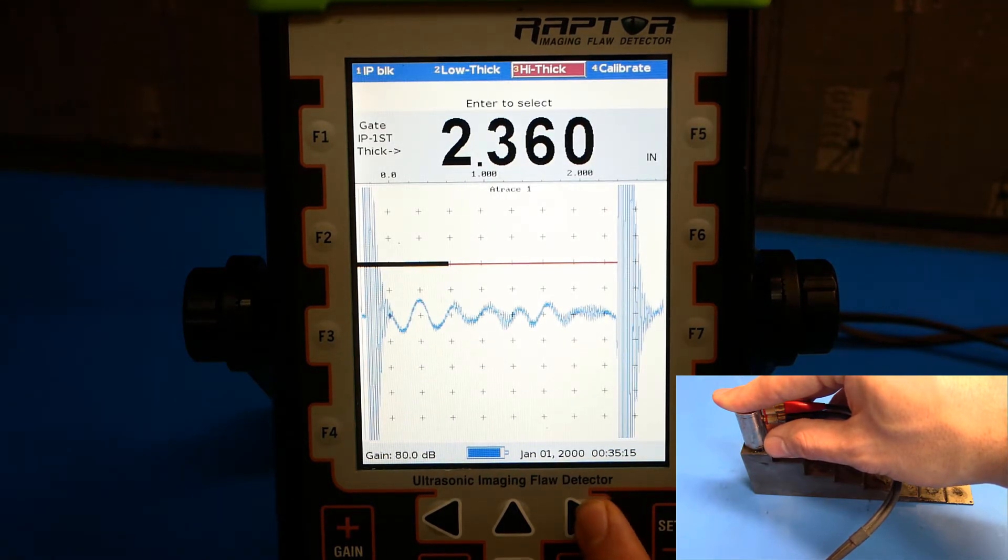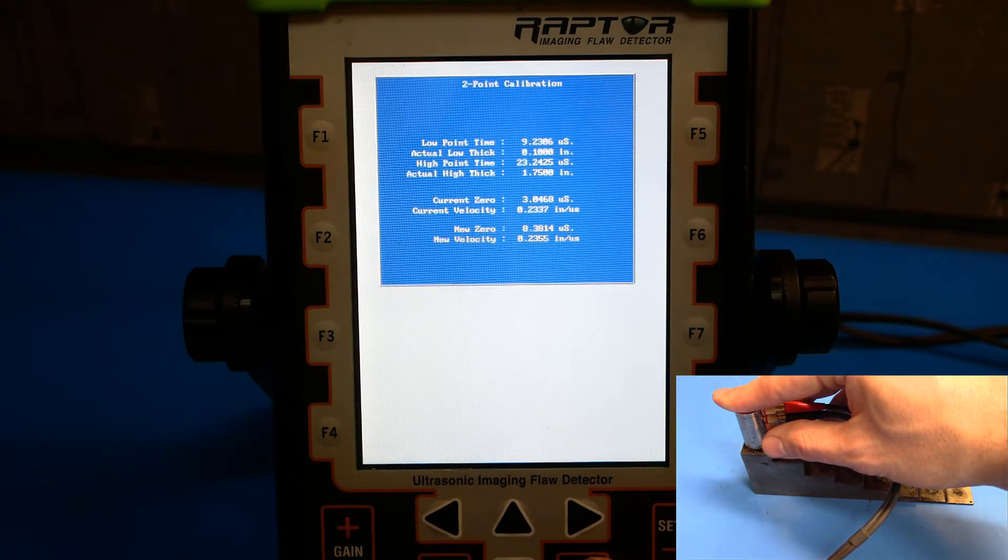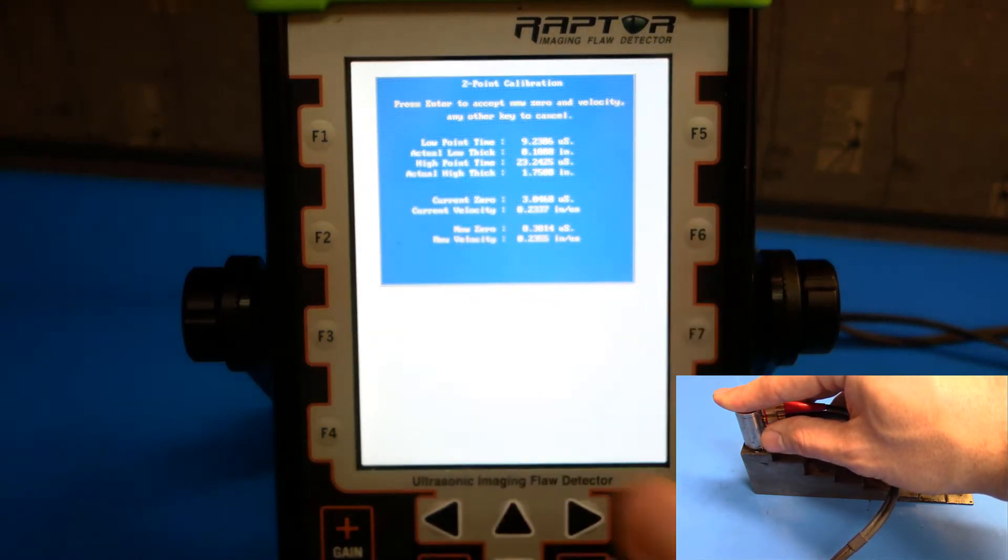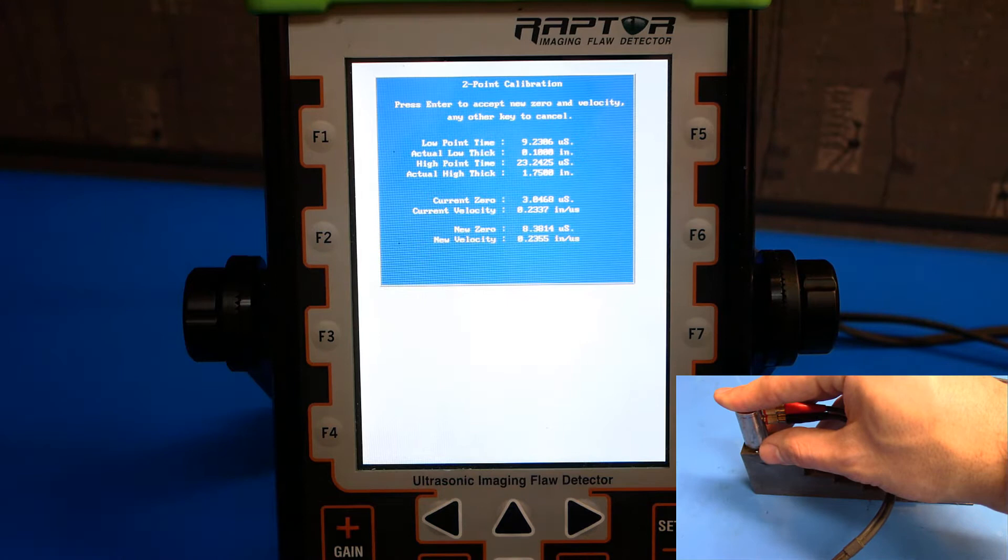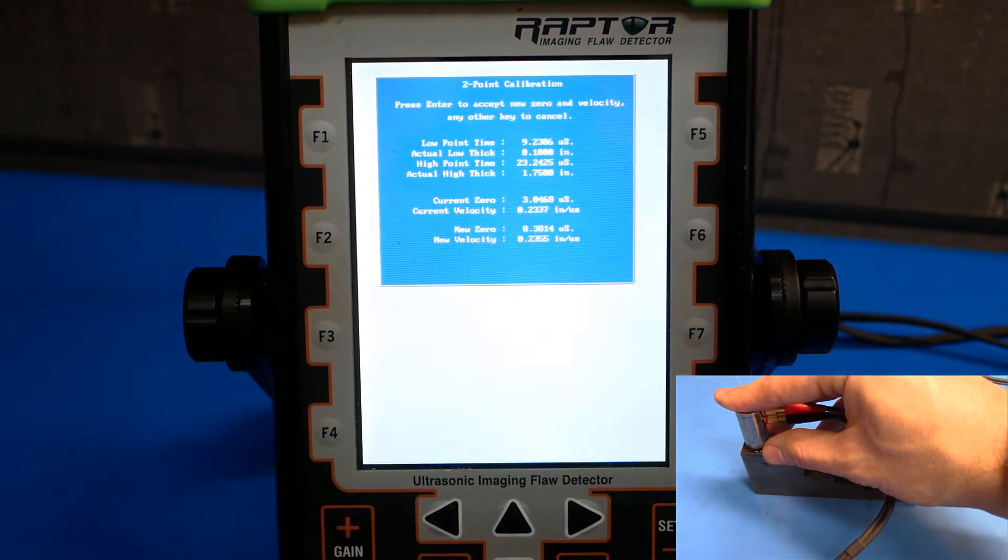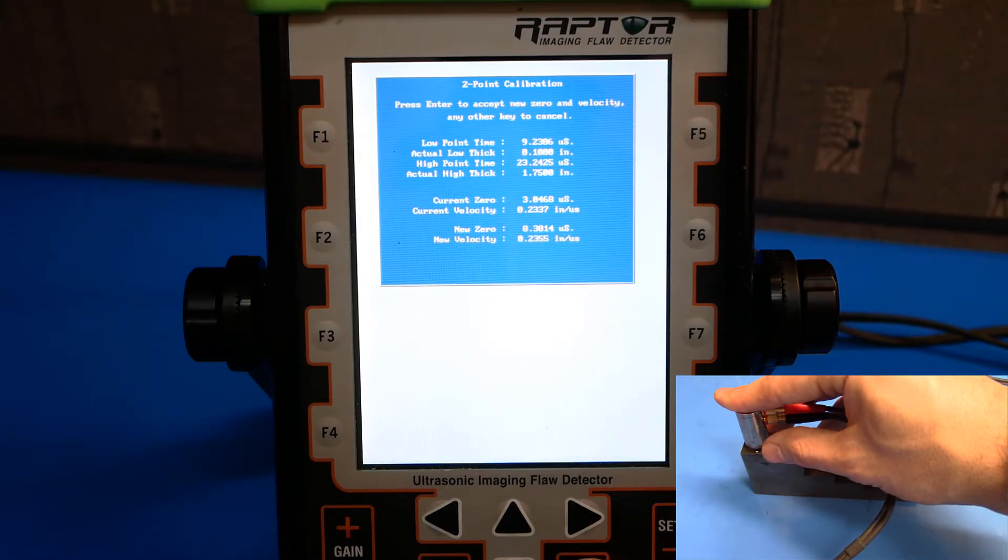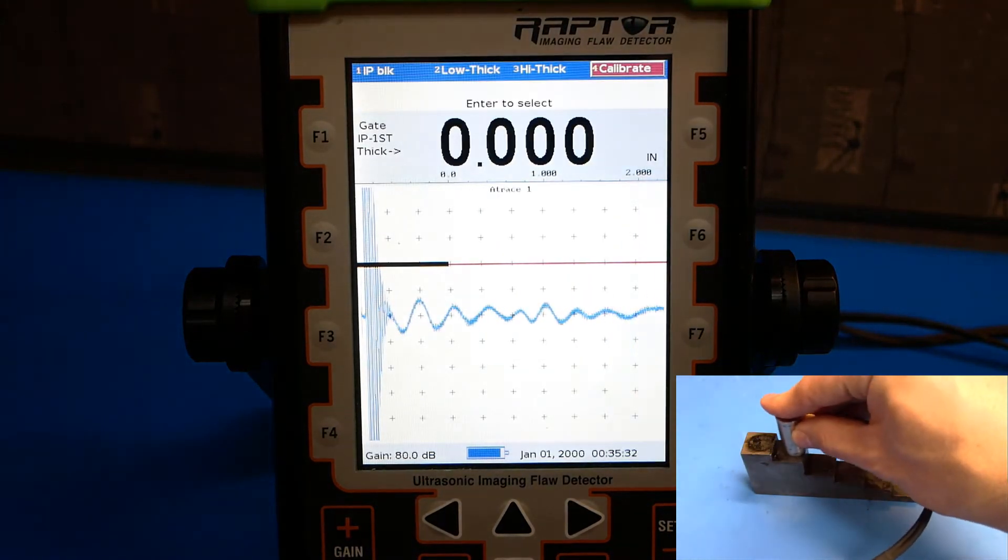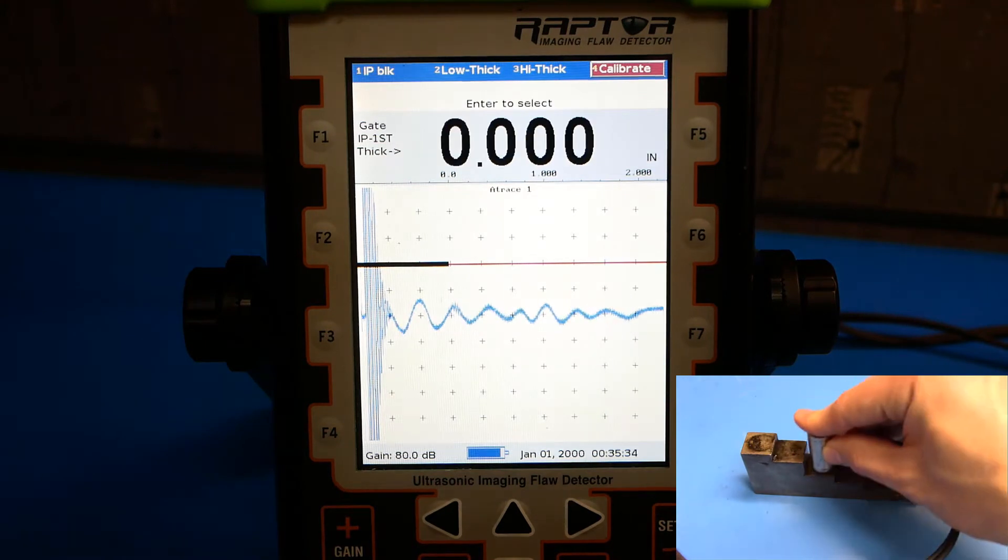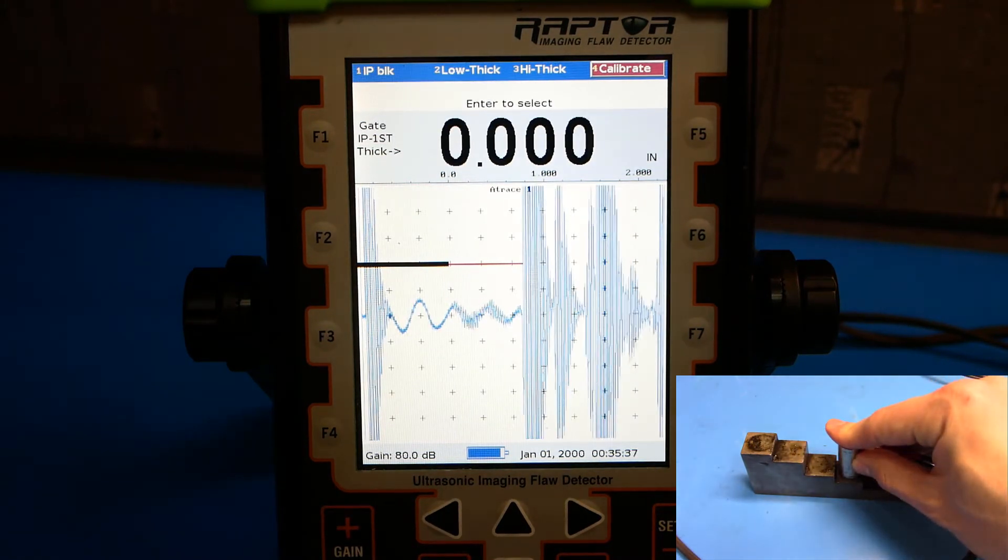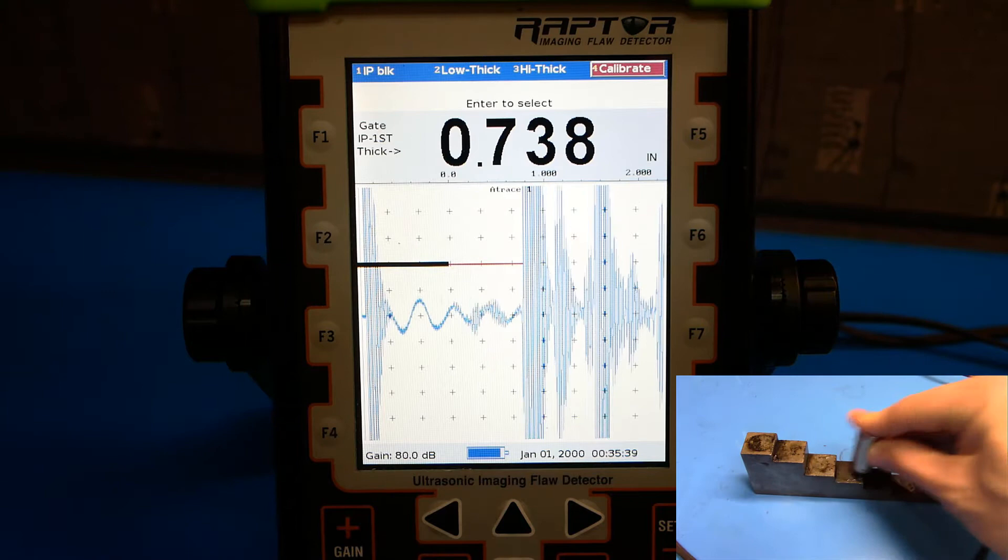After you've done that, hit calibrate. And the gauge will give us a list of adjustments that it's made, our new zero point, and our new velocity of sound. Push enter to accept. You can go through the step block to verify that the calibration is satisfactory.